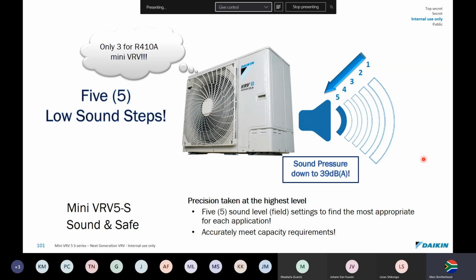Another advantage of the VRV5 is that if you live in a complex or something where people complain, or your outdoor unit's too noisy at night, you can set the sound pressure level down to 39 decibels. The 410 one only has 3 settings. The R32 VRV5 has 5. Okay, but bear in mind you're going to lose capacity if you lock your outdoors. If it's a very hot night and you're dying of heat, but your neighbor's complaining about the noise, it's a sacrifice because we are limiting the fan speed.